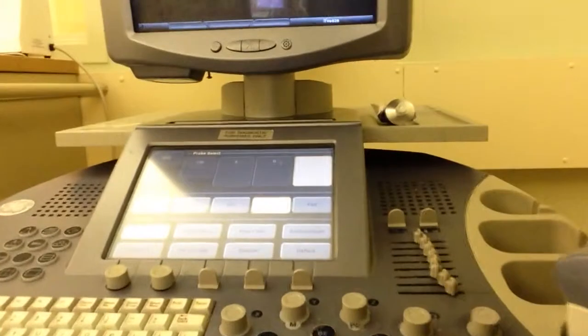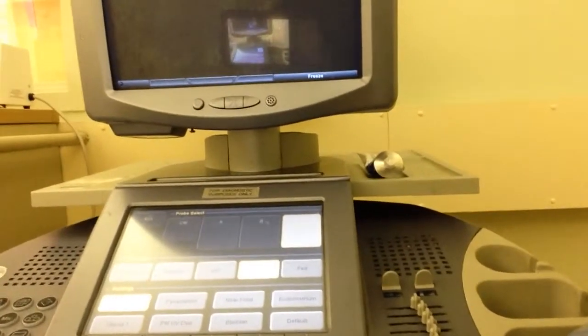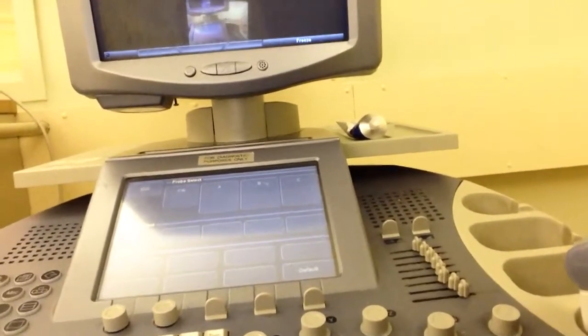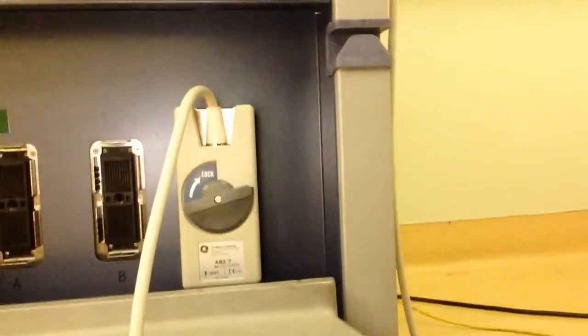And you can see on screen that there's a number of settings that the ultrasound technician can choose from. Now, what happens sometimes, and this is just a simple mistake, is you might not see anything on that screen. And why is that? Basically, they have no options. They can't choose anything. And they're wondering why. Basically, you want to ask them first, do they have the transducer locked into its port? When you go down here, you'll see that it's not actually locked. It's unlocked, and it can easily be removed from its base. When that transducer is not locked, the system automatically goes into a freeze mode and doesn't give the ultrasound technician any options.